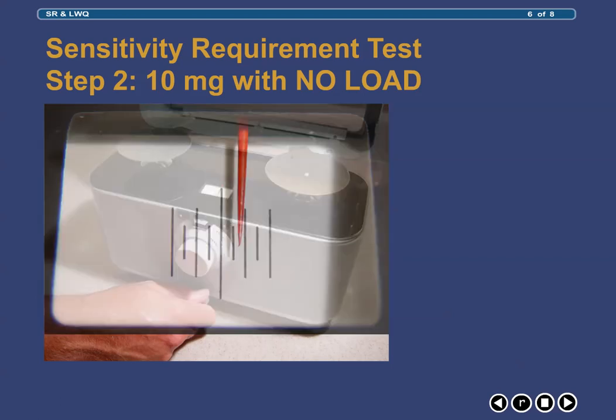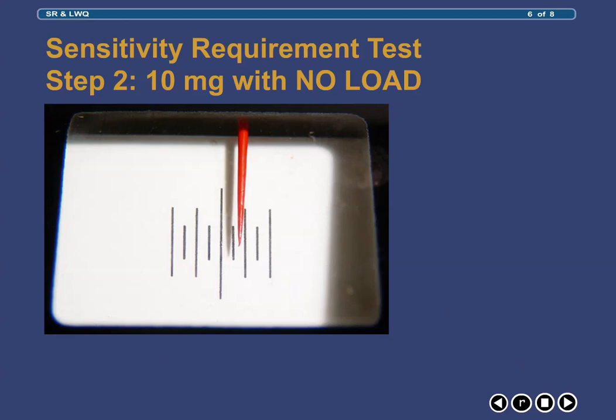Then observe the scale to see how many divisions the pointer has moved from its rest point. Using a 10 mg weight, the rest point on your pointer should move at least one and one half divisions as shown here, in order for your balance to pass this step in the sensitivity requirement test. At this point, you may be asking: why one and one half divisions?